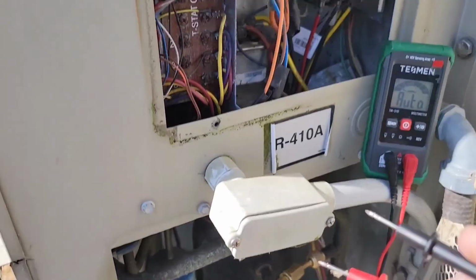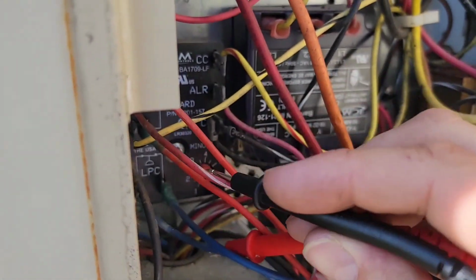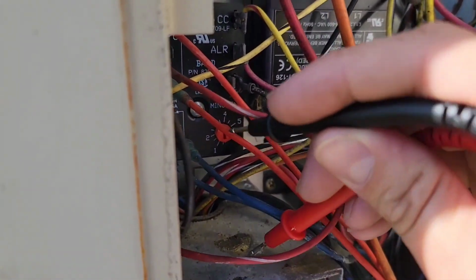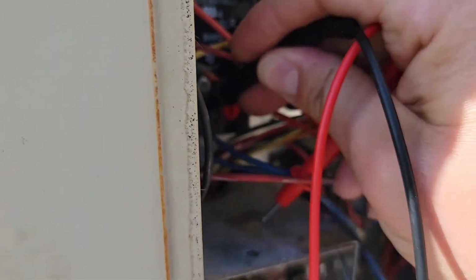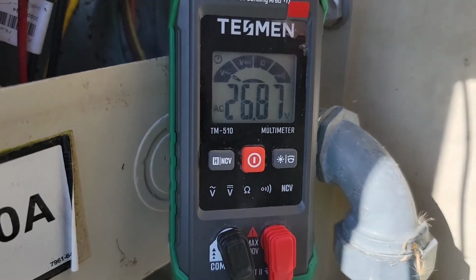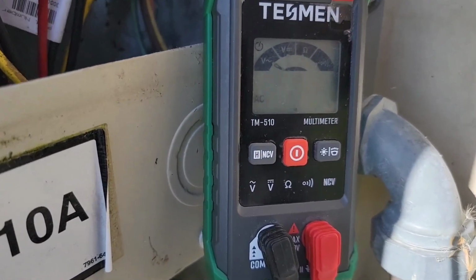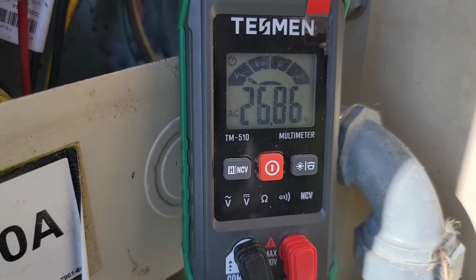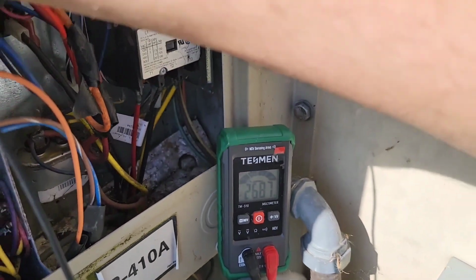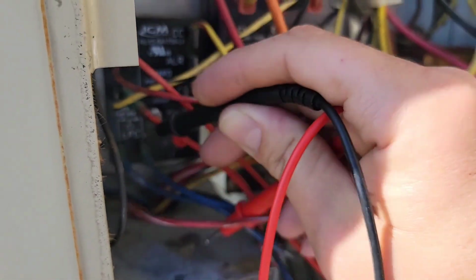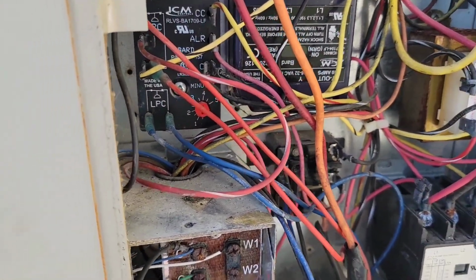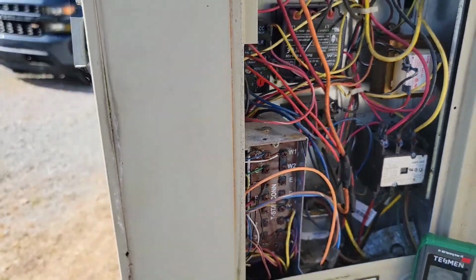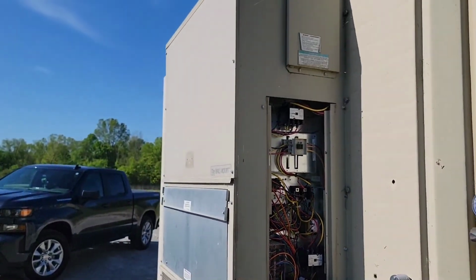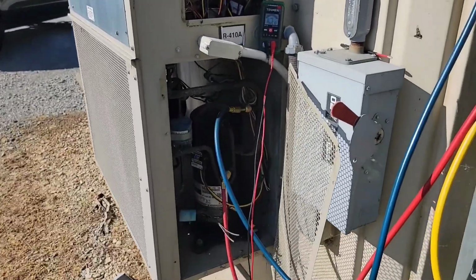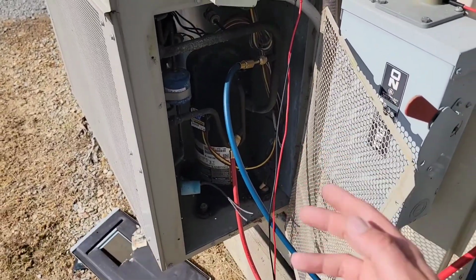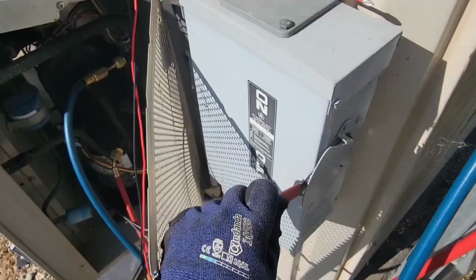Now what we can do is we can actually check across this low pressure control from common to each side. I'm going to check one side, got 26 volts. Check the other side, 26 volts, but I guarantee you that there was no voltage coming through this switch. So really need to open this thing up, check for oil, maybe get my leak detector, maybe get some nitrogen. We will figure this out.